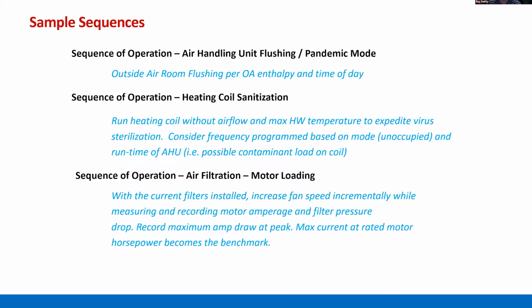On the air filtration motor loading, if you just have a VFD, you might be able to pull those numbers just to see in actuality whether a MERV 13 is going to hurt or harm. We've seen enough operations where dirty filters, when they're loaded up, do run similar to a MERV 13. We are not saying to have more filter changes. So those are things to think about. And then again, go deeper into the demand control ventilation based on how the design was done with the DOAS's and where that is. The goal now for you as practitioners is to use the tools that are in place. Most of the new designs are going to be updated, but it's now about how you use your existing sensors to start improving your indoor air quality.